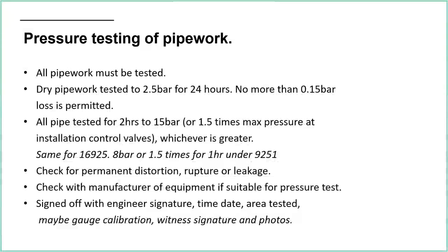What are you checking for? Well, you're checking for any permanent distortion, ruptures, which I imagine would be fairly obvious, or leaks. Now, I understand from residential and domestic, if you've got plastic pipe, I believe that they would do an air test first, because an air test is quicker, easier, and certainly less mess. So if you've got, say, CPVC pipe work, the major thing to watch out for is open ends. Your fitters have missed a bit, and there's a completely open end of pipe somewhere. You're going to find that pretty quickly either way.